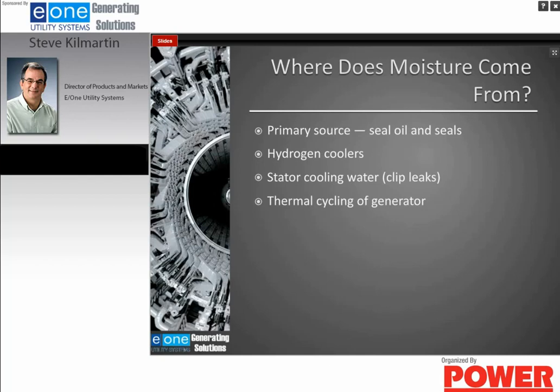You can get moisture from your hydrogen coolers. If it's a stator-cooled winding, you can get water from the stator cooling water. And again, you don't get moisture from thermal cycling, but the thermal cycling will cause condensation if there is moisture in the generator and it has a high dew point.